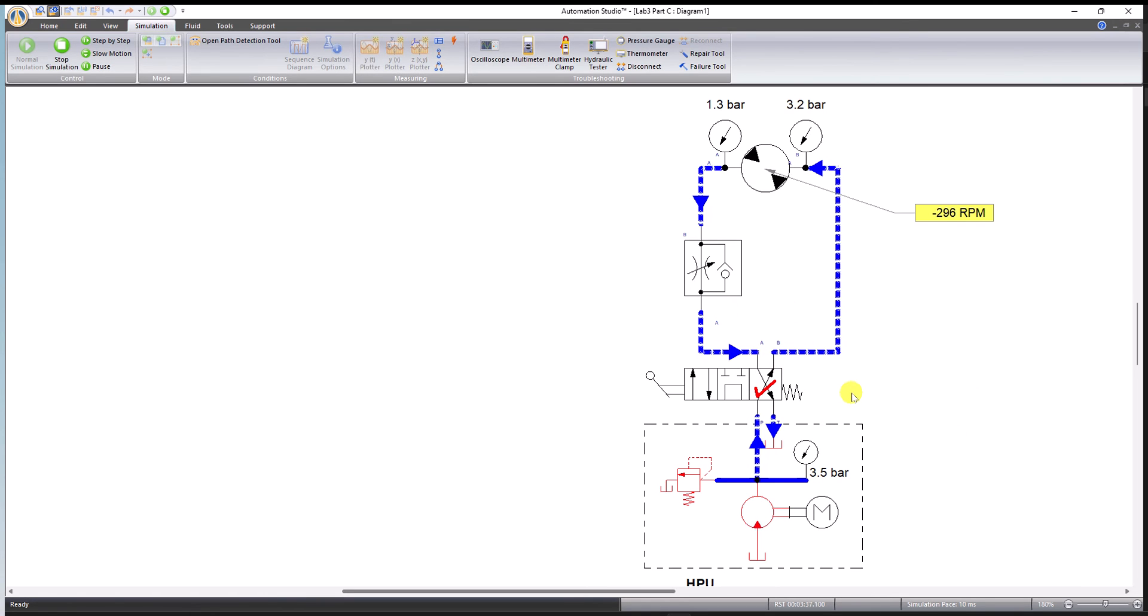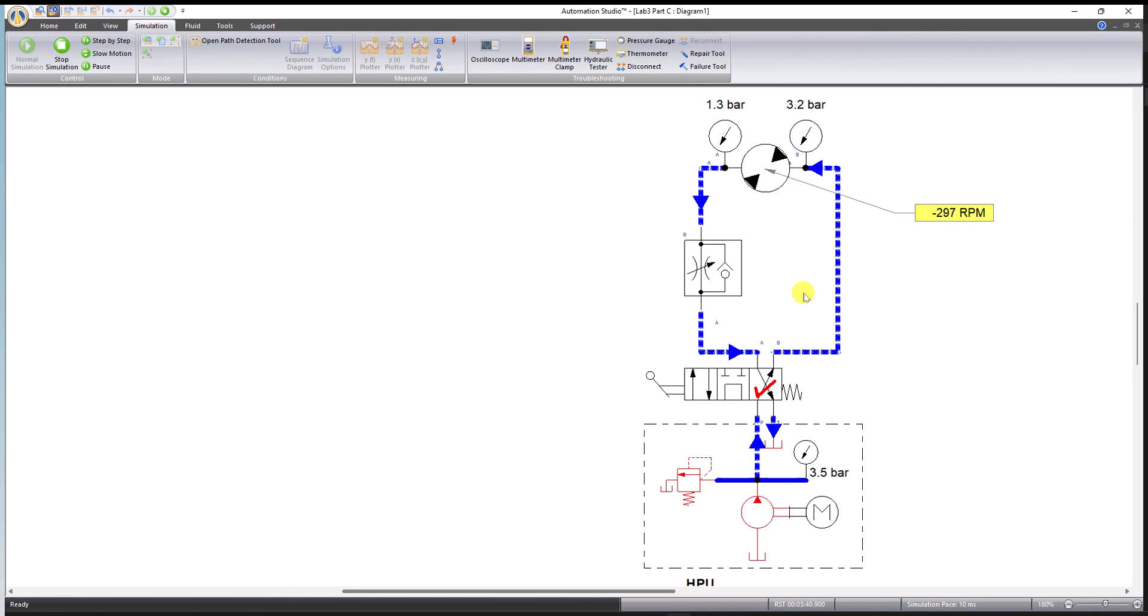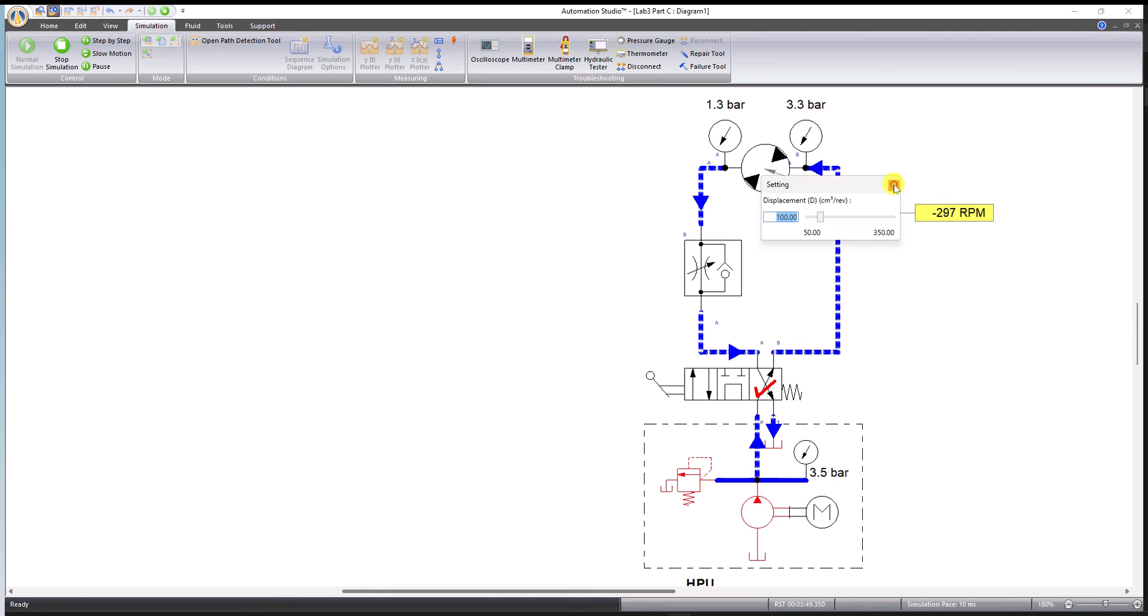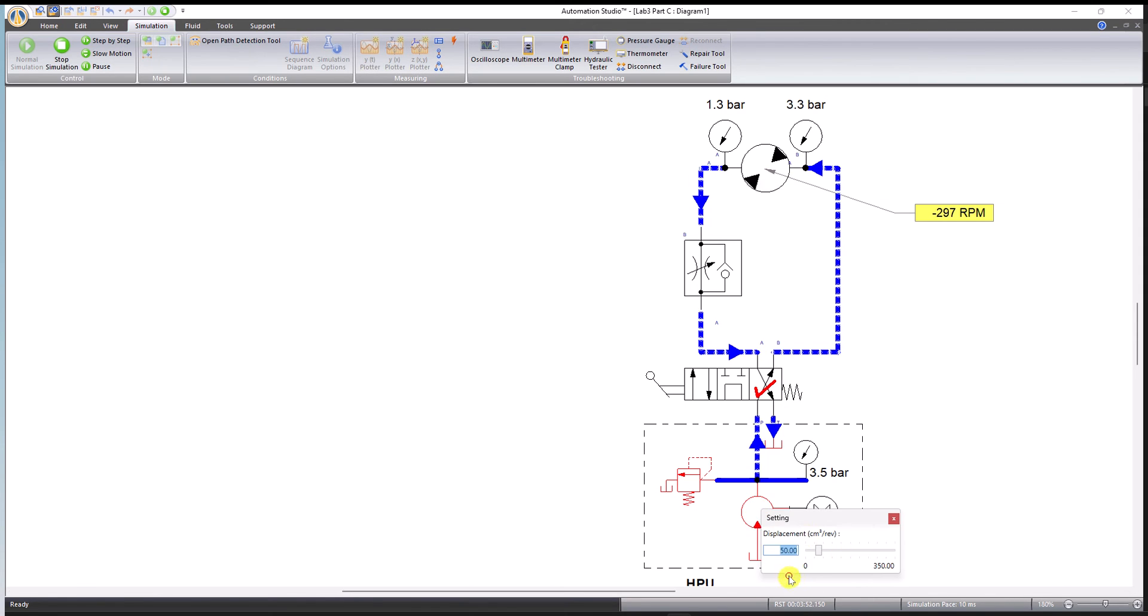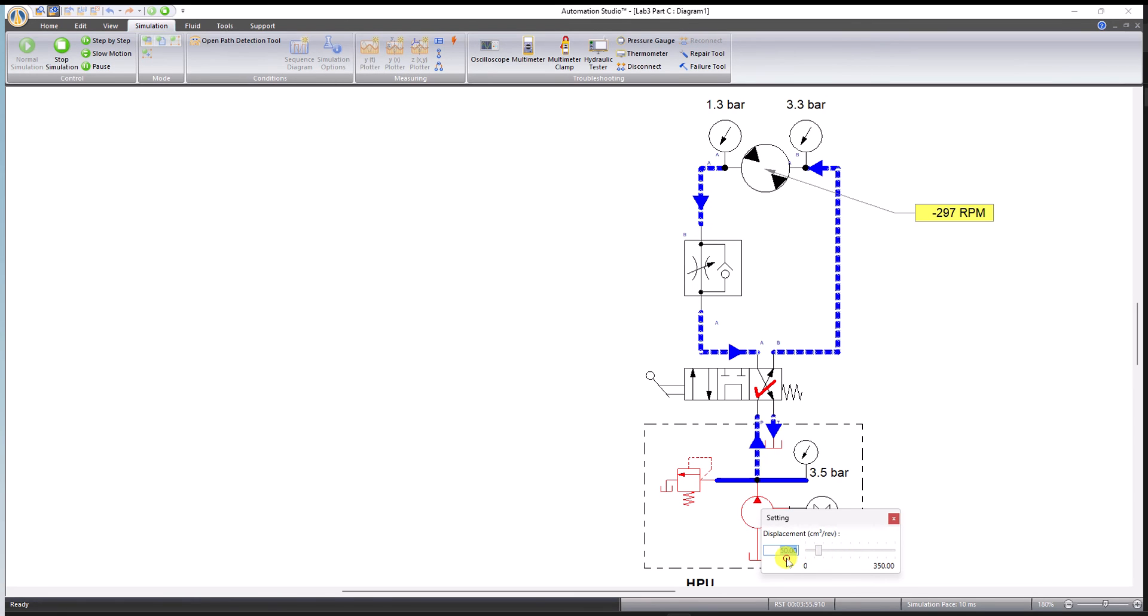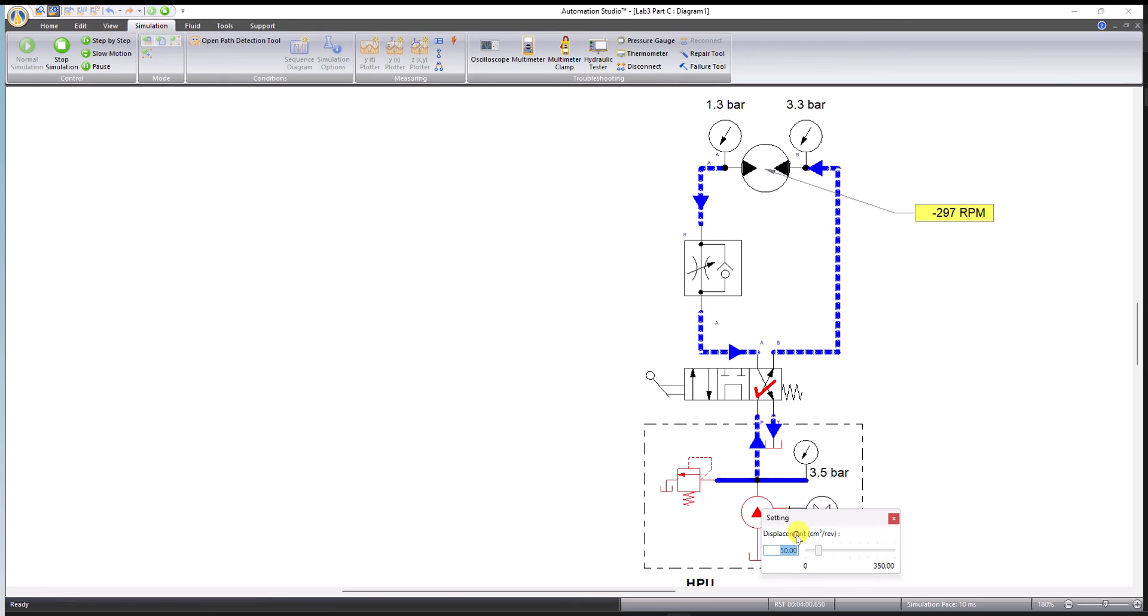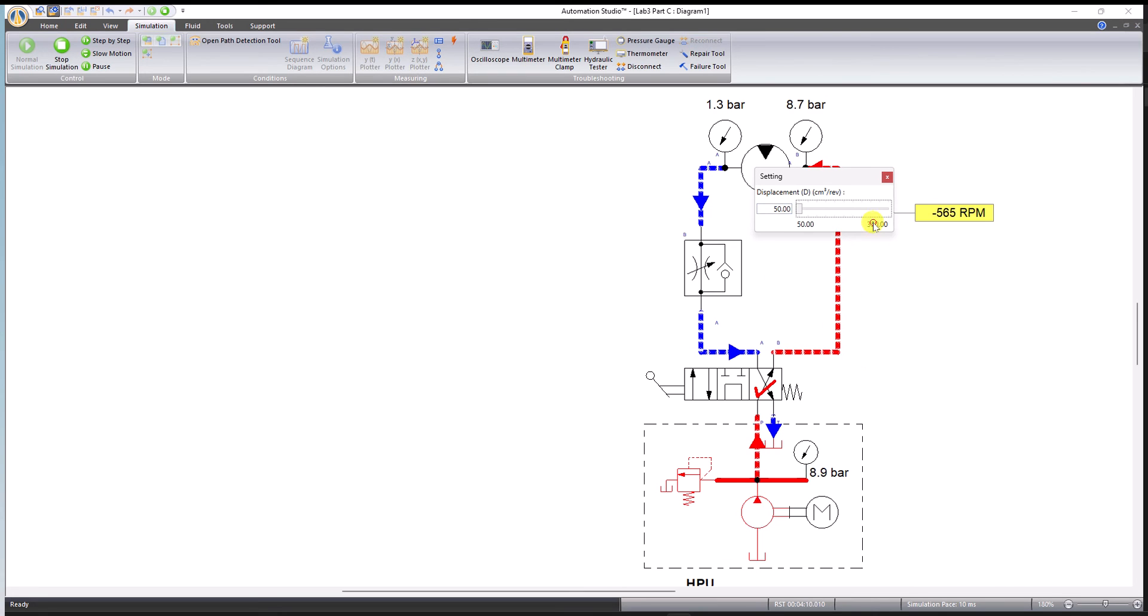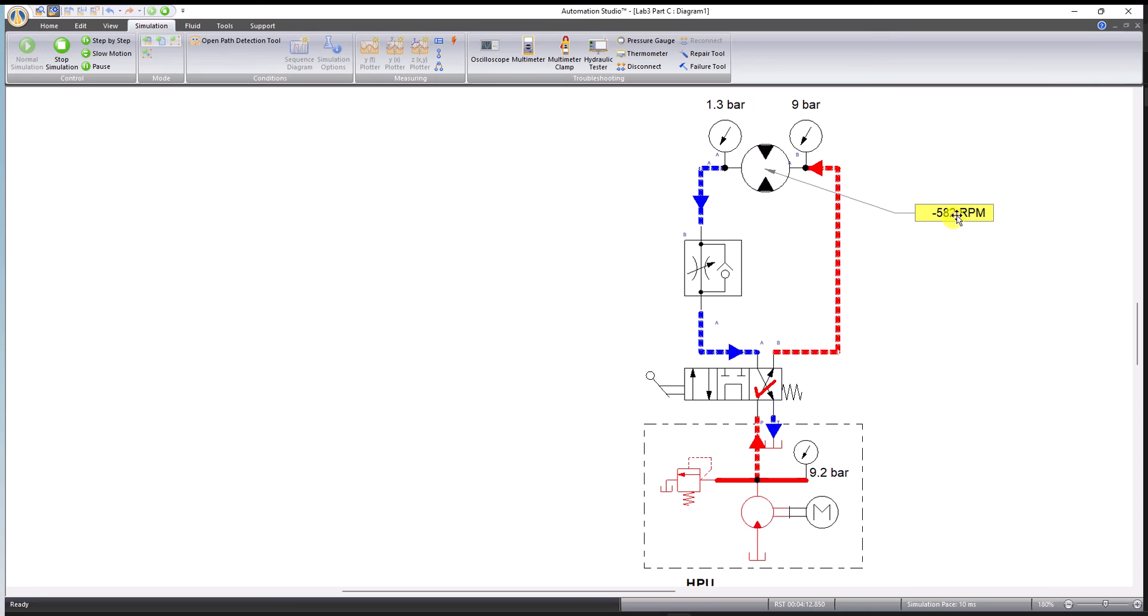This is how you can build this circuit and implement all those things. One way to ensure that the speed you're getting from the motor is good is to click and check what is the internal volume. This is 100 cubic centimeter per revolution. Check the same thing for your pump, this is 50 cubic centimeter per revolution. The pump is not producing as much flow as needed by the motor. To make things even, click the motor and reduce its size to 50. Now it is same size as the pump's internal volume, which will help to gain more speed. You can see immediately we have now 600 RPM in the clockwise direction.